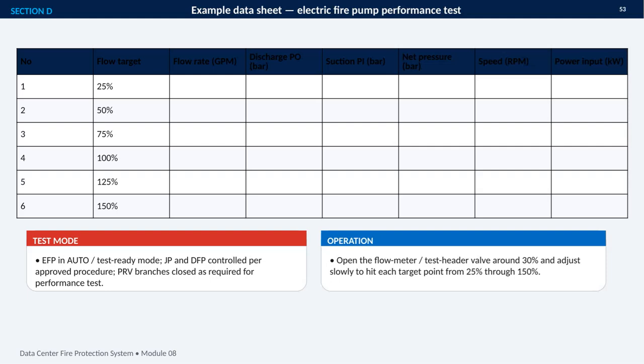This slide provides the data sheet for an electric fire pump performance test within the data center fire protection system. The table is organized around 6 operating points, from 25% through 150% of the target flow. At each point, the test record should capture the actual flow rate, discharge and suction pressures, calculated net pressure, pump speed, and power input. These measurements allow the pump's performance to be documented consistently across its operating range.